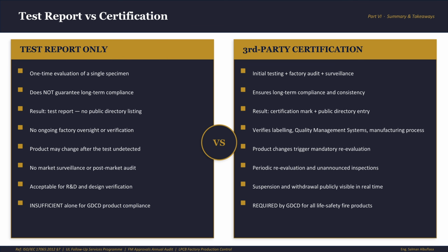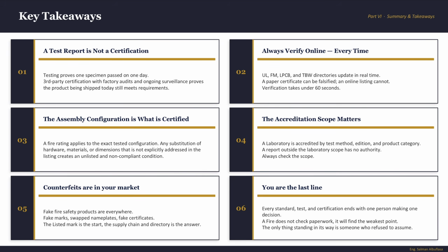And codes and standards will always require a third-party certification. They always refer to being listed. Listed means third-party certification. For key takeaways, starting with: a test report is not a certification. A test report is one specimen on one day. The factory could change everything the next morning and nobody would know. Third-party certification with factory audits, surveillance, and unannounced inspections is what proves that the product in your building today is still the same as what was tested. Do not confuse these two.